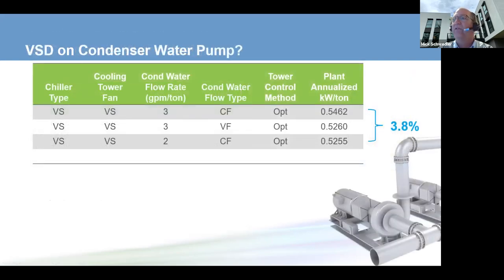Well, if it's a new system, we can design it with, again, a constant flow condenser water pump at the reduced flow rate of 2 GPM per ton. There's no magic number, but we get almost exactly the same savings as varying the condenser water pump on a plant designed at 3 GPM per ton. But in this case, there's no control complexity because we are not varying the condenser water pump flow rate, and we don't have to account for all those different operating conditions.